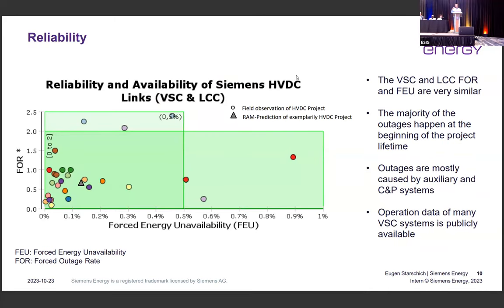Looking at the reliability, this is also one of the key features. Here is an overview of the reliability and availability of the Siemens Energy HVDC systems. The two key numbers to look for are what we call forced energy unavailability and the forced outage rate. So what does it mean? Forced outage rate means how many times the converter fails during one year. Is it one time, two times, etc.?